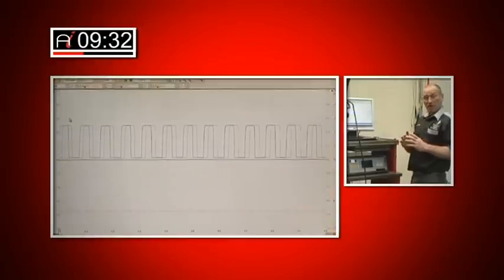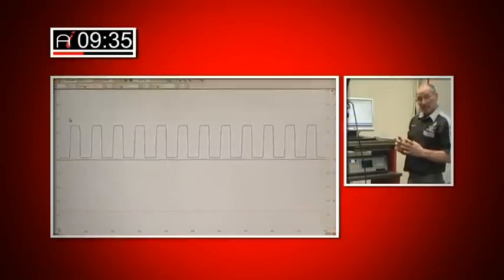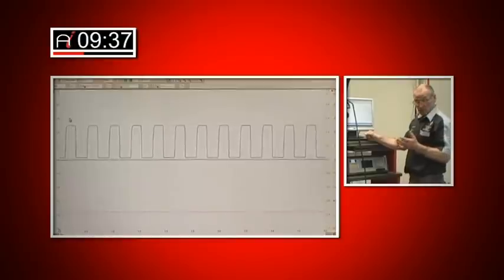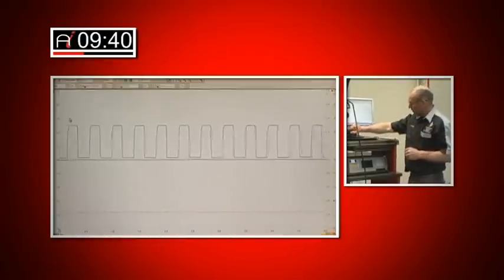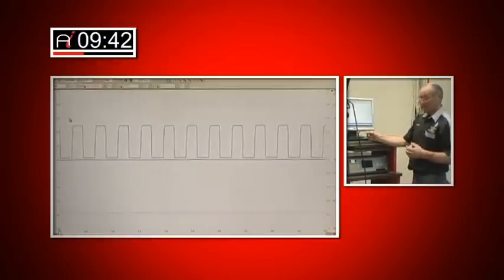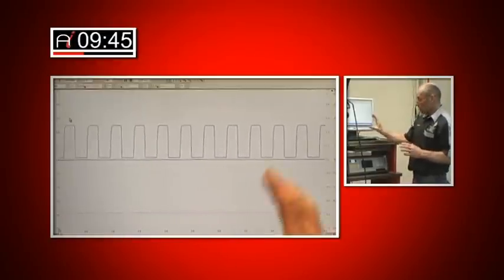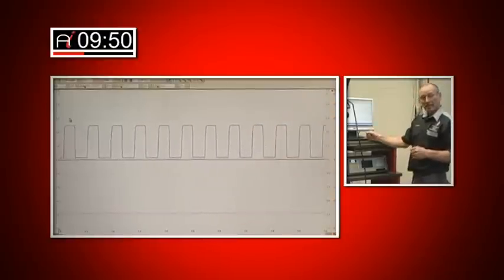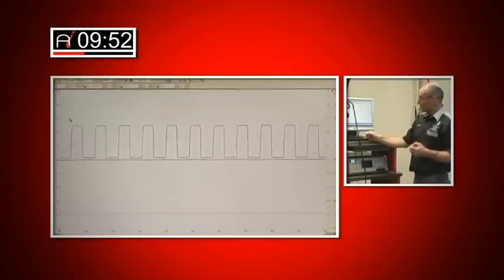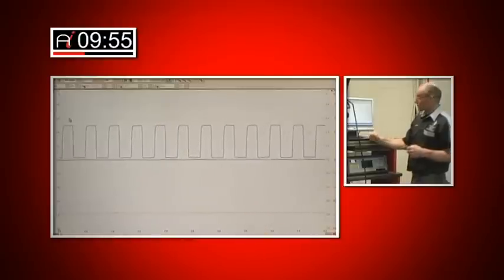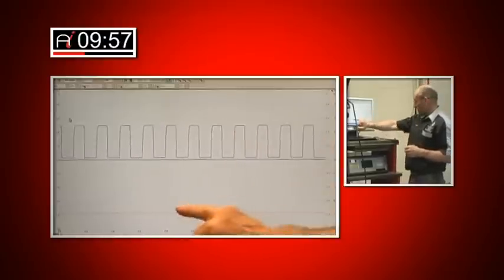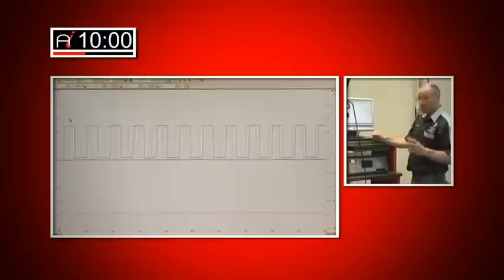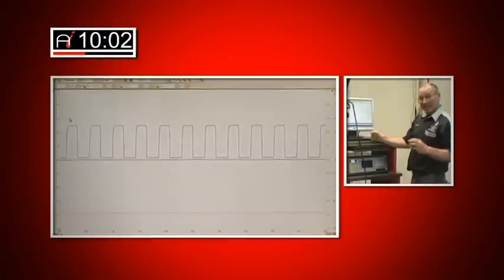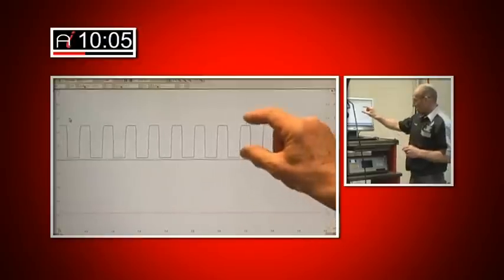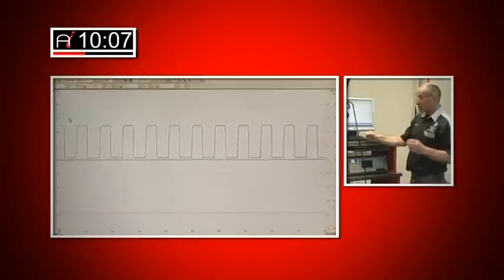And you can now see a very clear, easy to understand representation of the output signal from that air mass meter, and we also have the relevant frequency measurements as a digital signal. All of that is fine, but we can't mix those 2 signals in a format to do fuel trim analysis. The purpose of this demonstration is you can see that that signal has been converted very accurately to an analog representation. I'm going to leave that connected, although we're now not going to concentrate on that.